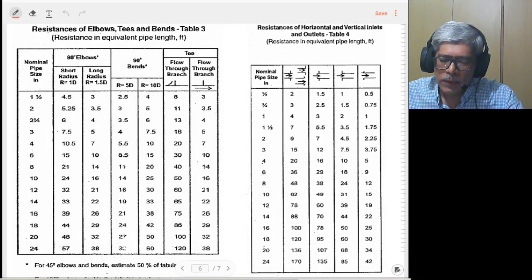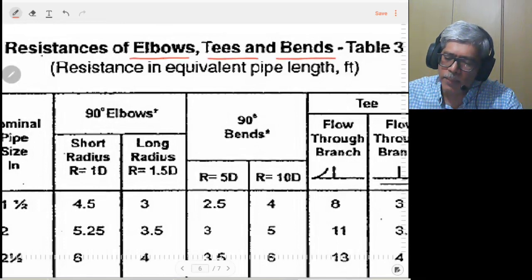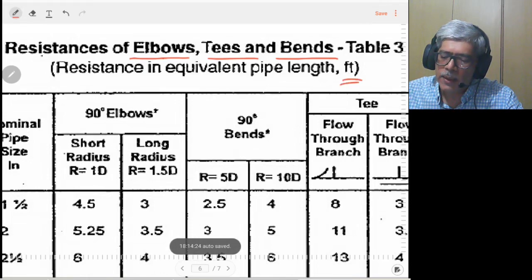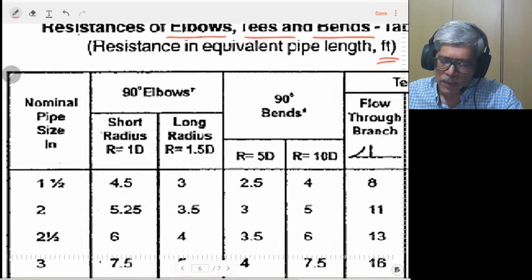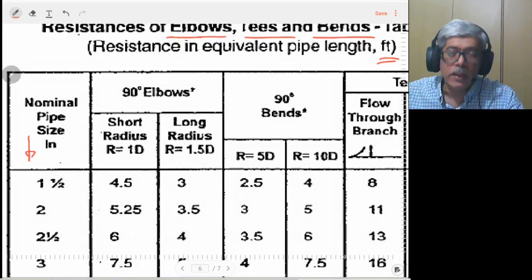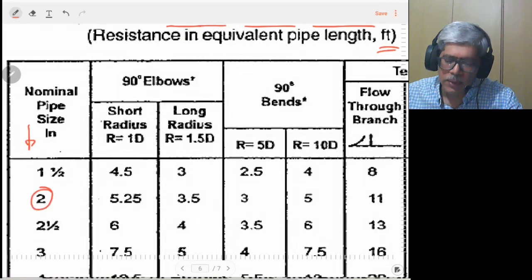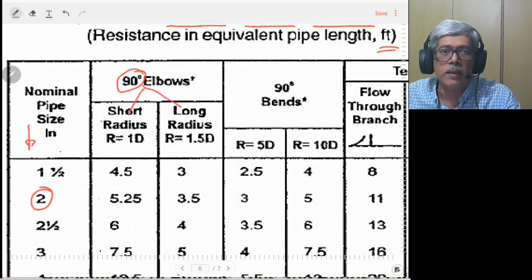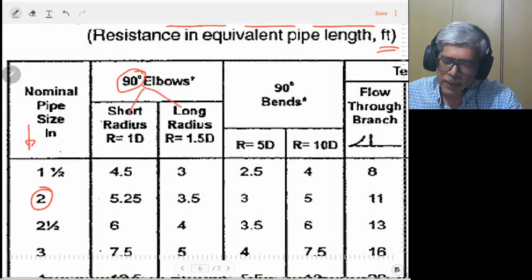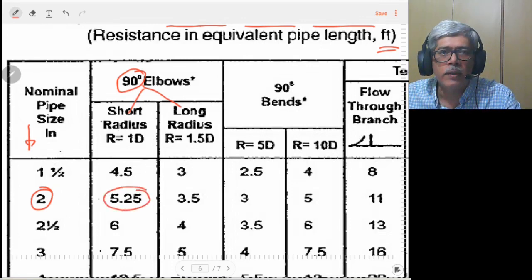Next we have the tees and elbows — different types of fittings — for which the equivalent length, again in feet, is given by this particular table. The first column is pipe size. If you have a two-inch pipeline and a 90-degree elbow, we have short radius elbows and long radius elbows. If you have a short radius 90-degree elbow of two-inch size, its equivalent straight length is 5.25 feet.